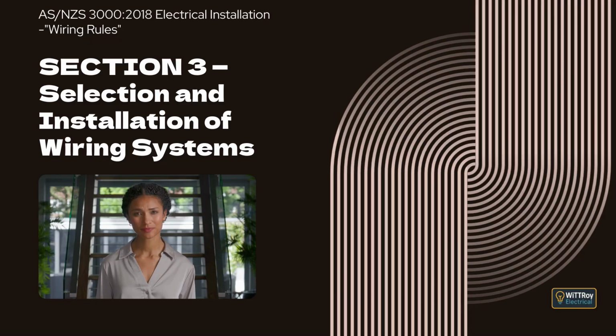Where several cables are associated together, such as single-core cables used in a multi-phase circuit, the cables must be arranged in accordance with Clause 3.9.10.3. The circuit must be clearly identified at the switchboard where it originates so it is obvious that the circuit uses an ESR system. No switch is allowed to operate in the combined protective earthing and neutral conductor of an ESR system. Only electrical fittings that are specifically identified as suitable for use with an ESR system are permitted to be used. Circuits that use ESR systems cannot be protected by RCDs.